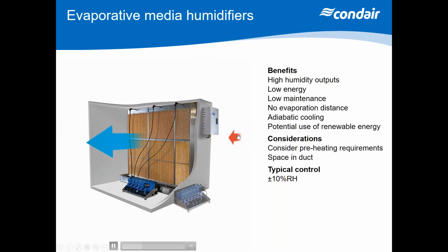The beauty here is that they're low energy. About 270 watts runs this, because all you're running is a panel and a hydraulic module. It's low maintenance, it forms part of the water system, so it has to be chlorinated once every 6 months. But apart from that, the flushing of the material should keep any mineral deposits on the material to a minimum. And there's no evaporation distance, because all the water is evaporated off the surface, so there's no water droplets.